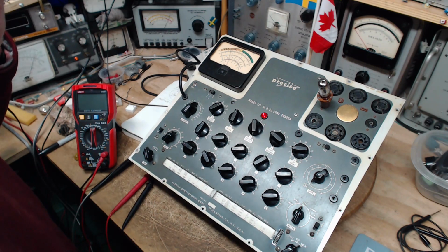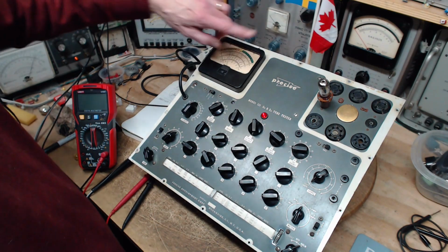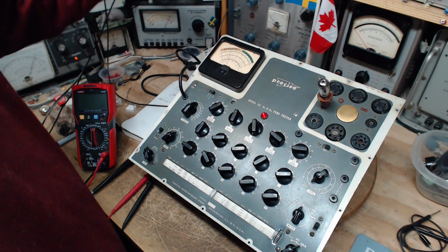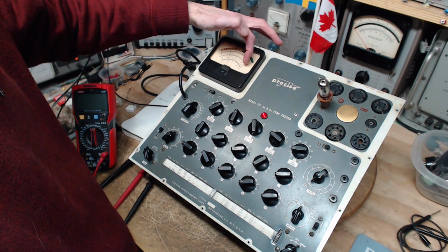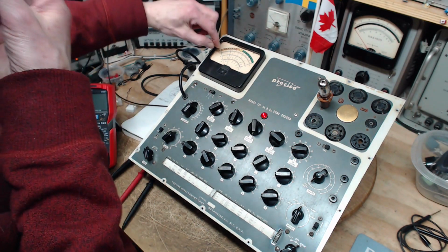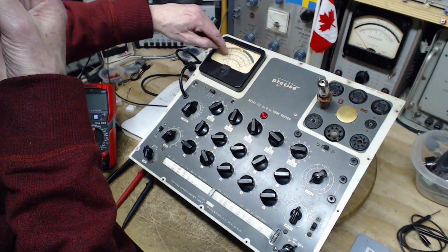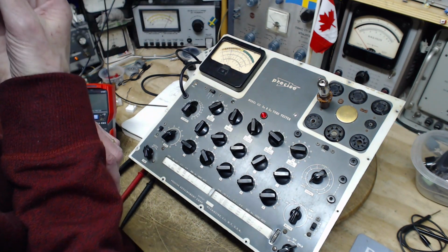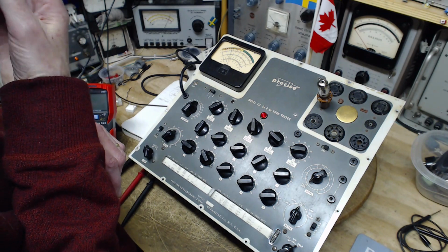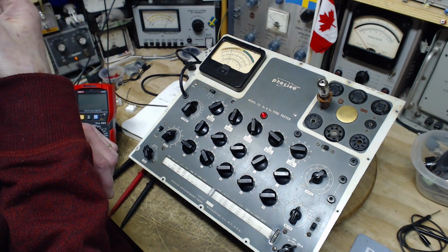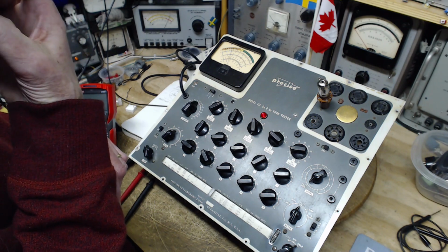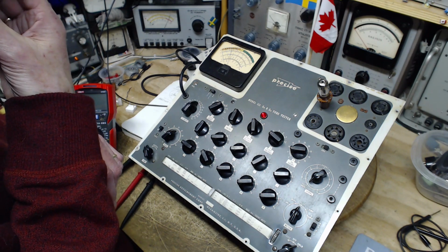Ready to test. Test. I think we got a higher reading this time. So now we're on the 3 scale, reading... yeah, before it was 400, now it's 500, 600, 700, 800. 800, but the reject point is 1300. Wow, that's just not giving me any kind of good feelings at all. Not at all.